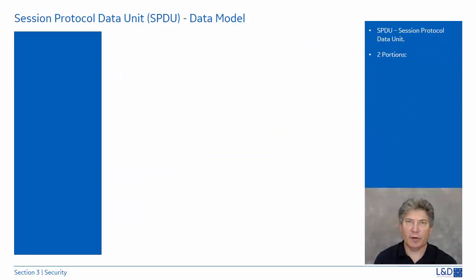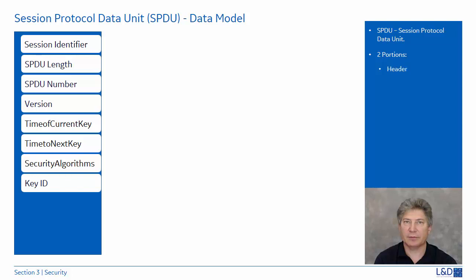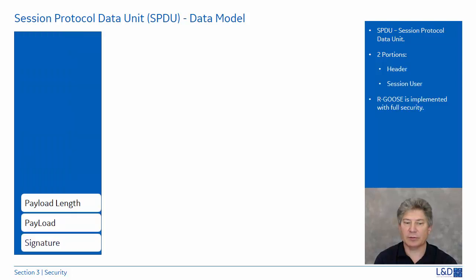With all the security defined, the routable GOOSE is encapsulated in a very neat data packet. 61850-90-5 provides the capability to convey messages in a data packet known as the Session Protocol Data Unit, or SPDU. This supports secure tunneling of the Ethernet-based GOOSE to facilitate easier exchange between substation and control centers. It has two portions: a header and a session user.